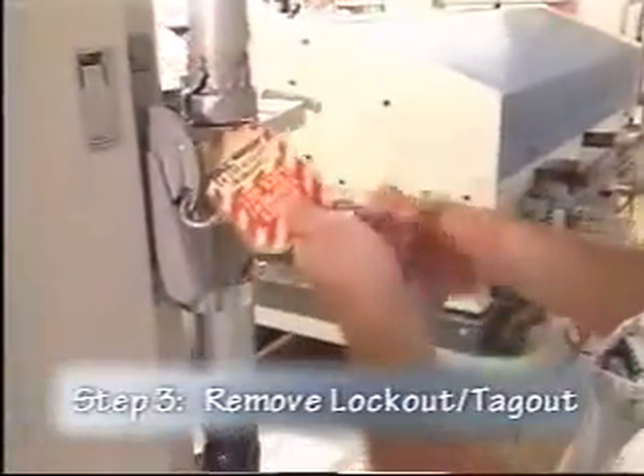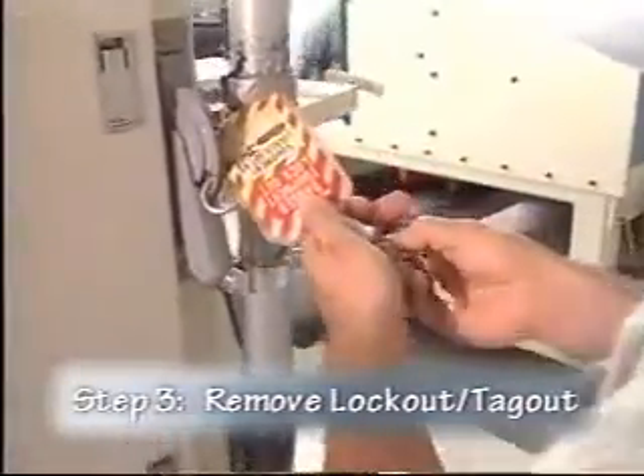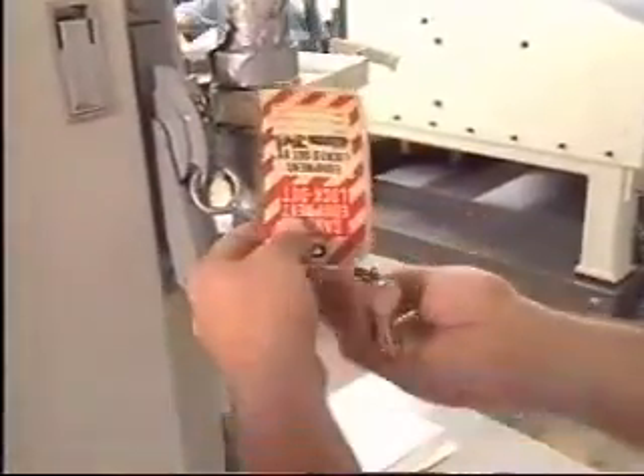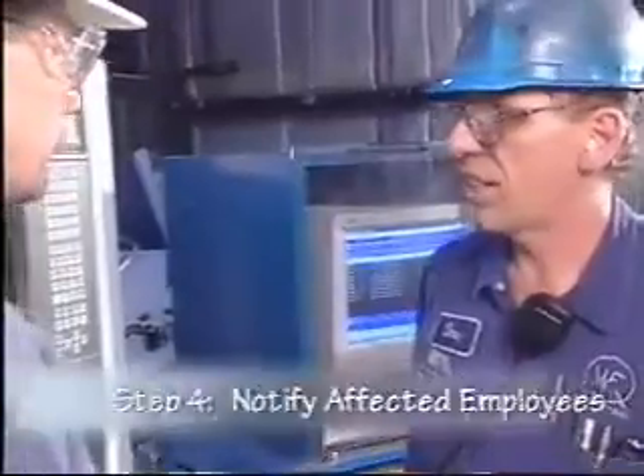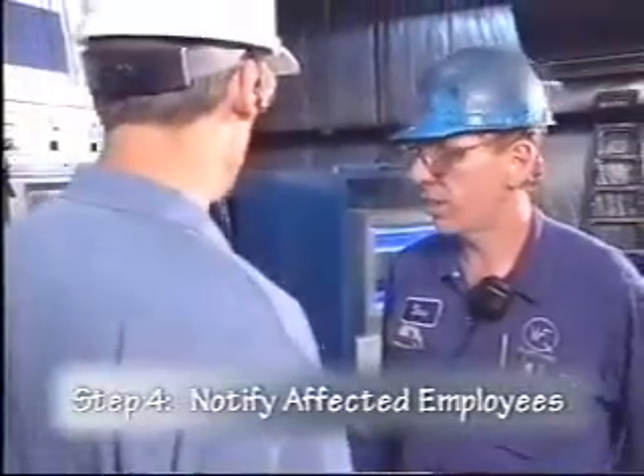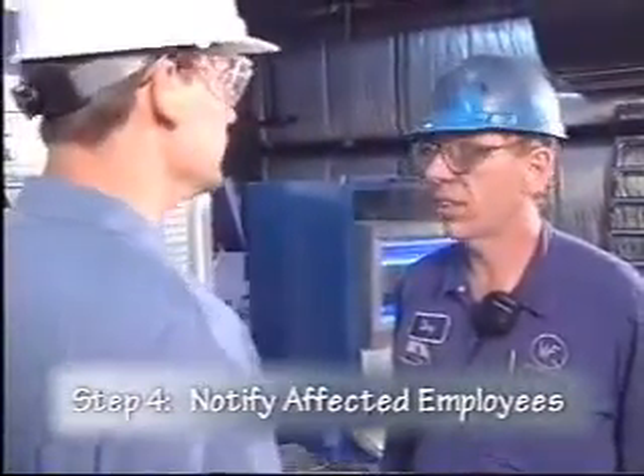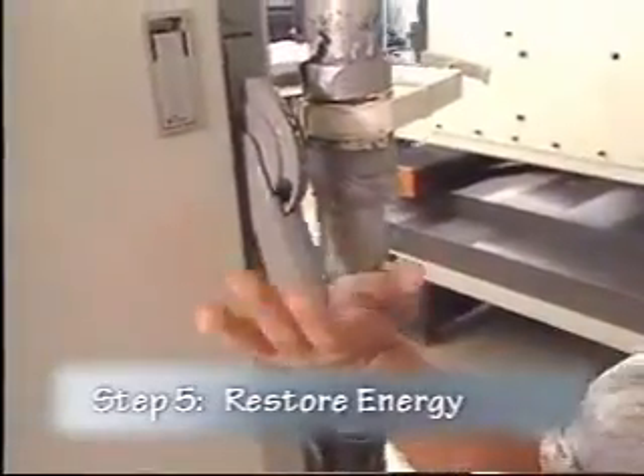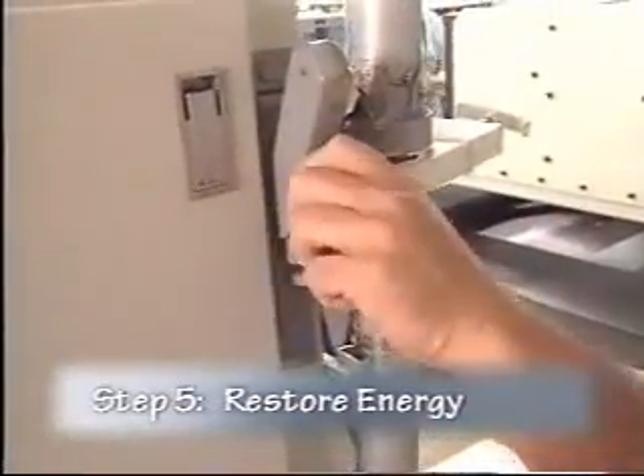Next, remove the lockout-tagout devices. Each person must remove his or her own lock and tag. Before you restart the equipment, notify all affected employees that the lockout-tagout devices have been removed. And finally, restore energy to the equipment.